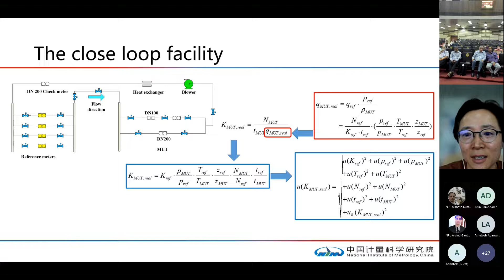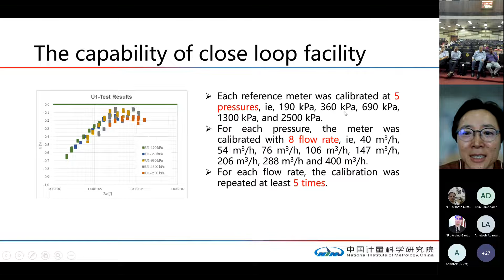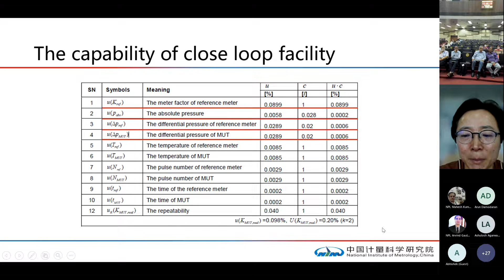The challenge for the closed loop facilities, like the sonic nozzle facilities, is how to achieve the best calibration result and make the curve fit. Finally, according to the principle of turbine meters, we make 5-point pressure calibrations for each turbine meter. For each pressure, we calibrate at least 8 flow rates. So finally, the uncertainty for the closed loop facility will achieve 0.2%.